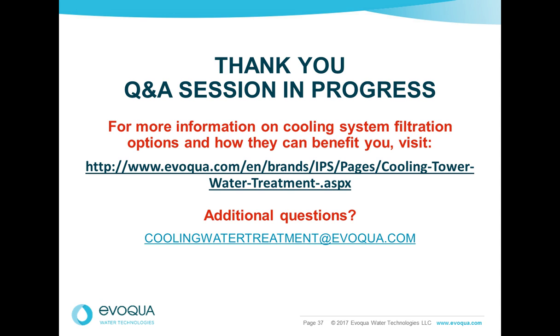How about this? I have screens in my tower sump. Is that good enough for tower filtration? The screens are there to collect... Go ahead, Bob. The screen picks up ragweed and cottonwood and stuff like that, but it really doesn't affect the dirt and particles that foul the heat exchangers. I'm going to say categorically that screens are inadequate unless you've got something like a 1 micron screen in a filter device.